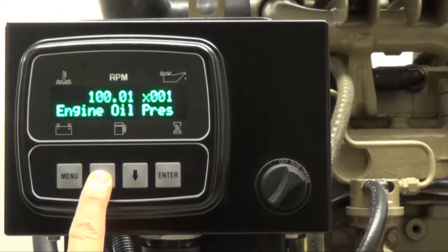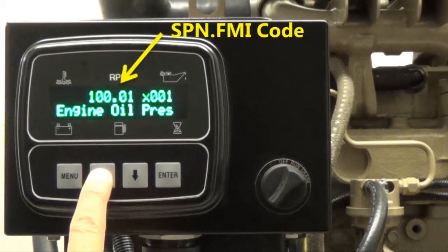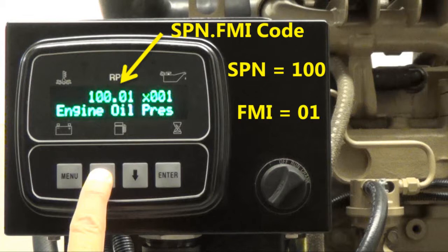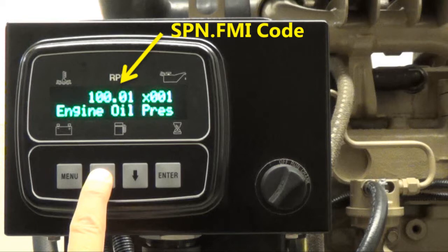The second engine oil pressure code is identifiable with a SPN.FMI code of 100.01. Once again, the SPN code 100 identifies a problem with engine oil pressure, but this time the FMI code .01 specifies low oil pressure to the degree of a major engine fault, which would have triggered a red alarm and engine shutdown. If you are having trouble identifying SPN.FMI codes, please contact Controls Incorporated.